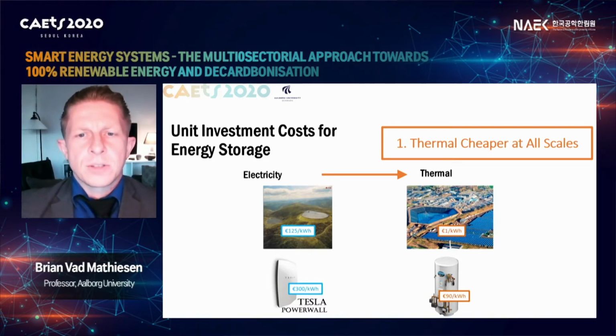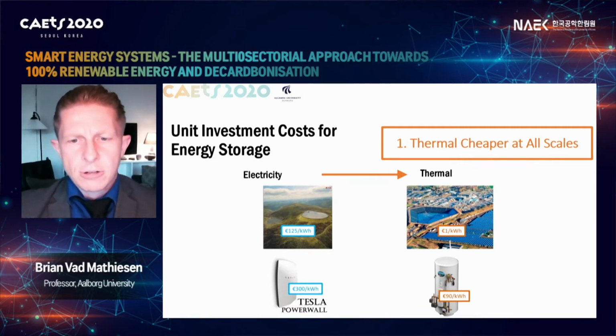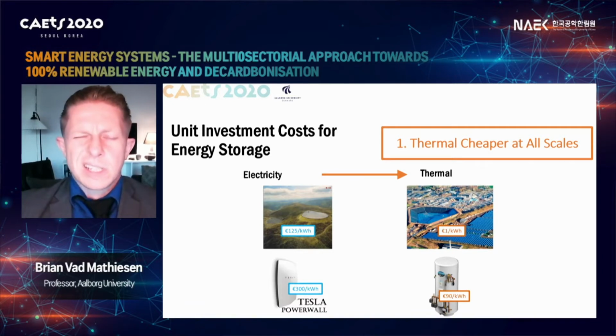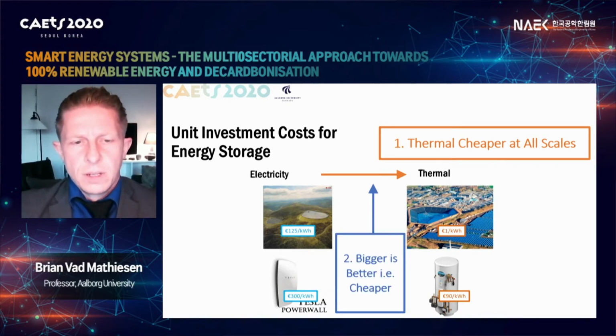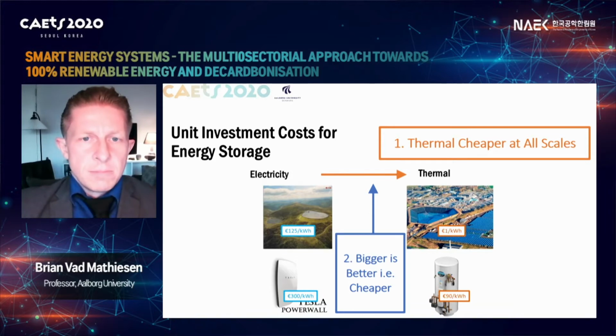If we compare this to thermal storages, we can have a large pit storage, which is 1 euro per kilowatt hour, or a household level storage, which in effect is not very flexible, because when it's cold, it's cold in all the houses. But here the costs are much lower than electricity storage. So we see a tendency that thermal is cheaper than electricity, but also bigger is cheaper in both cases.